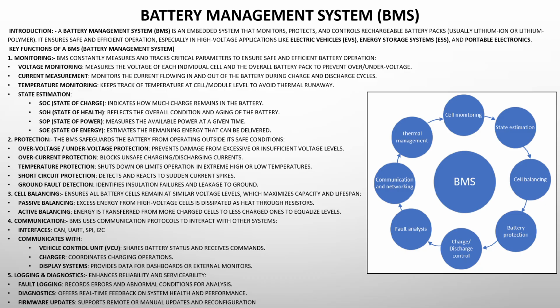Job two is protection, the bodyguard part. It actively prevents the battery from going outside its safe operating limits, things like overvoltage, undervoltage per cell and for the whole pack, overcurrent, and temperatures too high or too low. It also looks for short circuits and ground faults, major electrical safety hazards. If it spots danger, it can cut off the power or limit the current, whatever's needed to keep things safe.